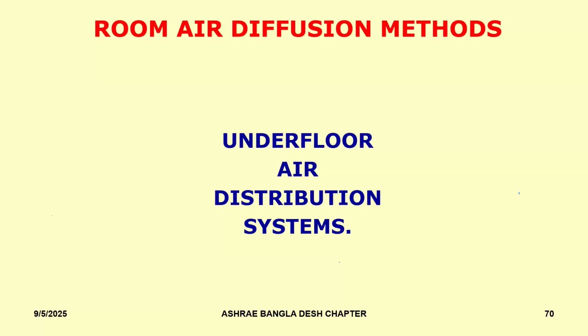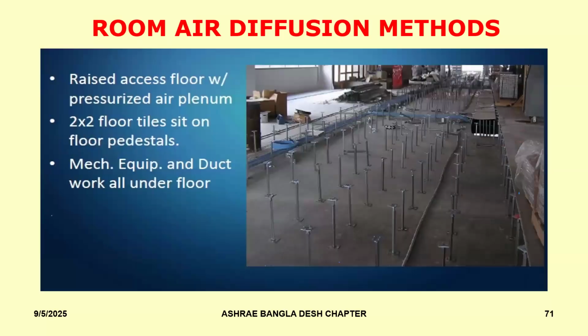So that was a fully stratified system. Underfloor air distribution will help us in two ways. It's not a fully stratified system. It's partially mixed and partially stratified. So if you see the way the system works, you'll get a better understanding of that. So what we do is we create a false floor, just like you have a false ceiling. We create a false floor, and we can either pressurize the entire false floor plenum with the clean conditioned air, or we can have ducts running below the false floor to make sure that the air is distributed.